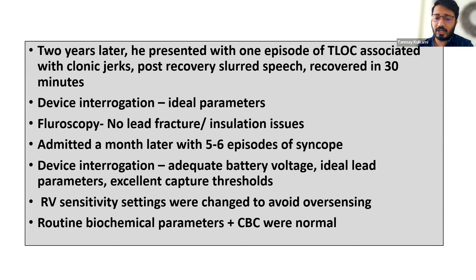He was admitted a month later, again with 5 to 6 episodes of syncope. That time, device interrogation revealed adequate battery voltage, ideal lead parameters, and excellent capture threshold. RV sensitivity settings were changed to avoid oversensing, considering the close proximity of the abandoned RVOT lead with the present RVOT lead, and to avoid lead-to-lead interaction. Routine biochemical parameters and CBC were normal.